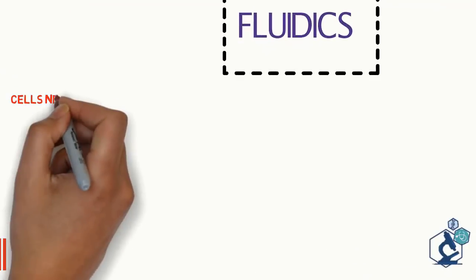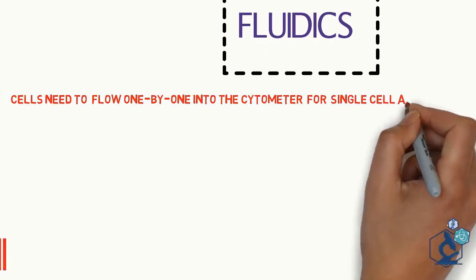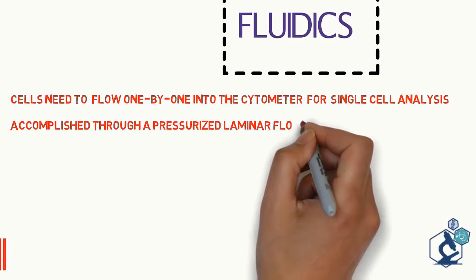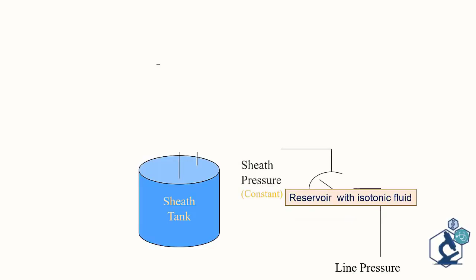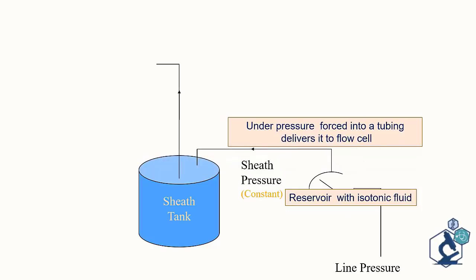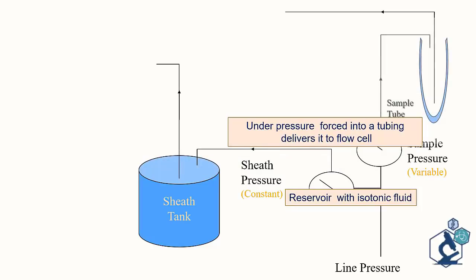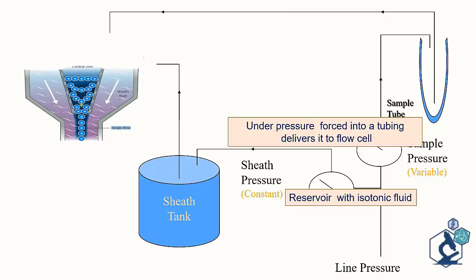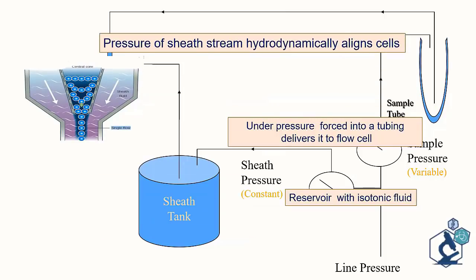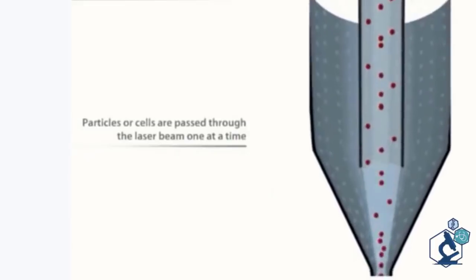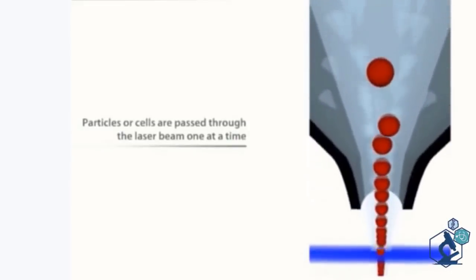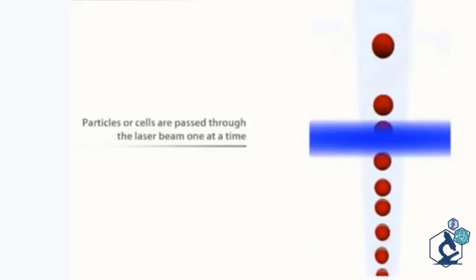So let's begin with fluidics. The cells need to flow one by one into the cytometer to do single cell analysis which is accomplished through a pressurized laminar flow system. The sheath tank is a reservoir with isotonic fluid which under pressure is forced into a tubing which delivers it to the flow cell. Sample is also injected into the flow cell at variable pressure. Sample fluid flows in a central core that does not mix with sheath fluid. The pressure of the sheath stream hydrodynamically aligns the cells so that they are presented in a single file to the light beam. The introduction of a large volume of fluid into a small volume in such way that it is focused along an axis is called hydrodynamic focusing.